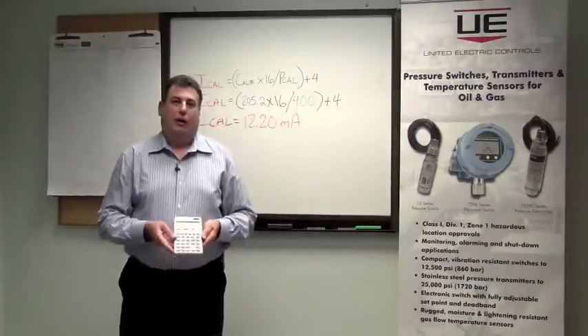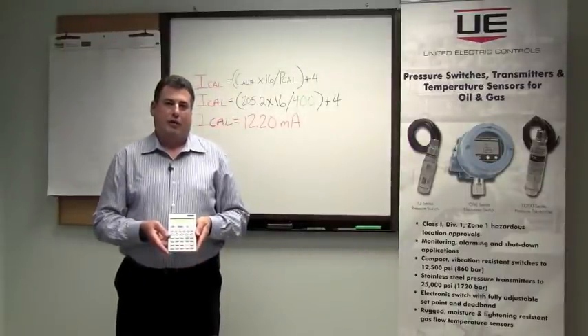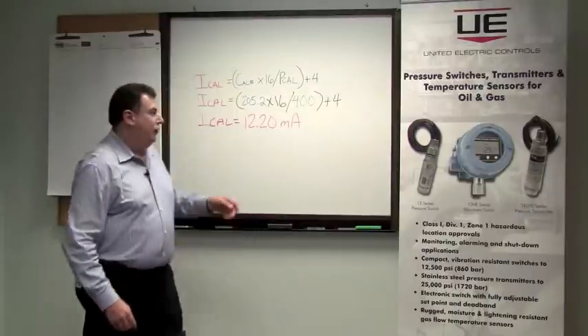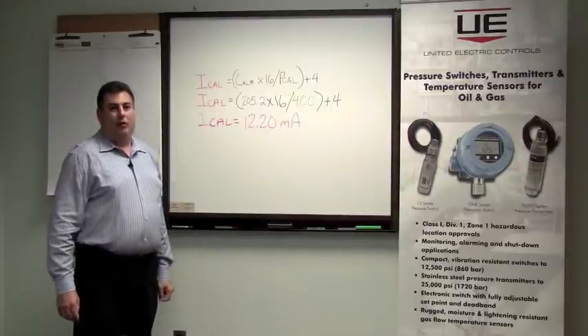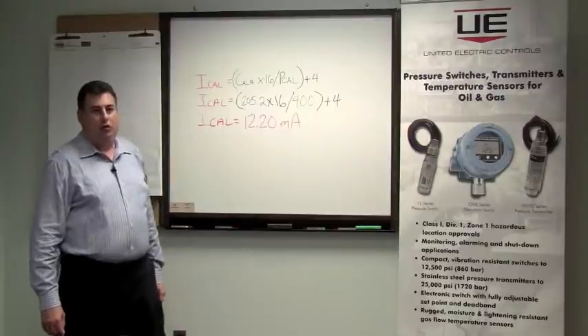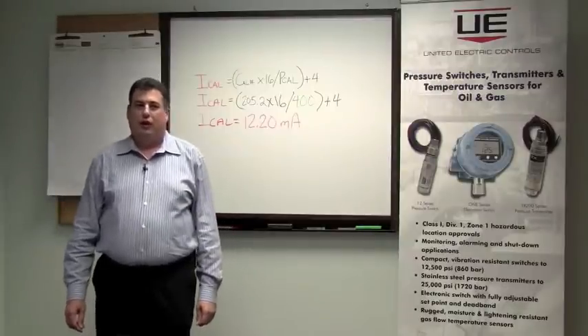We'll also need a calculator in order to perform some basic math to figure out how to range the TX200. The following formula is used to calculate the ICAL, which will be used to range the transmitter. The ICAL is the current output, which the user will set to achieve the desired range or PCAL.